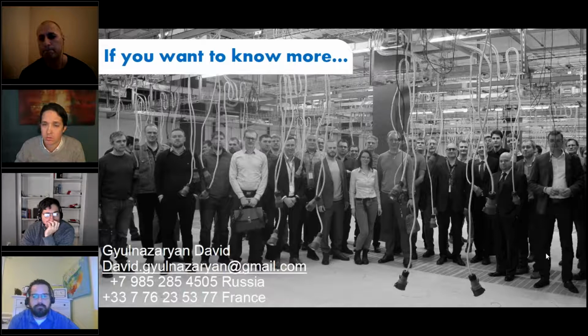So the liquid heat pipe, your liquid heat pipe is contained by the servers? LHP, you mean a loop heat pipe? Yes. Loop heat pipe, it's a closed loop, without any water inside. It transfers the heat from the processor to the end of the rack in a passive way, so it's dry. But there's a liquid loop inside the server. It's a self-contained capillary loop with a two-phase transition. Yes, yes. There are different kinds of ammonia used.